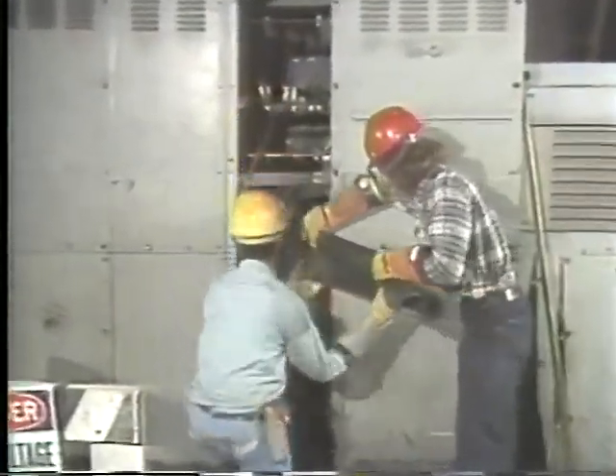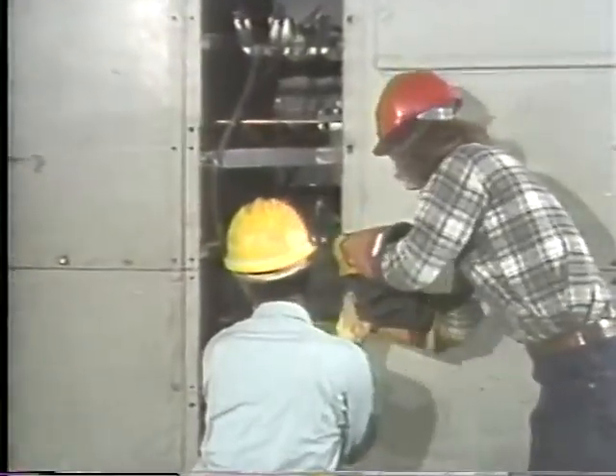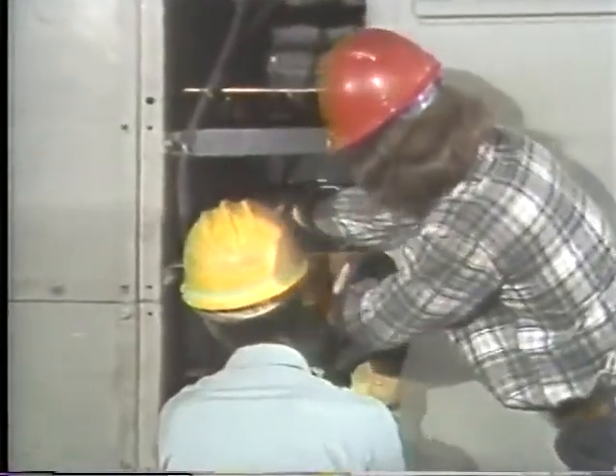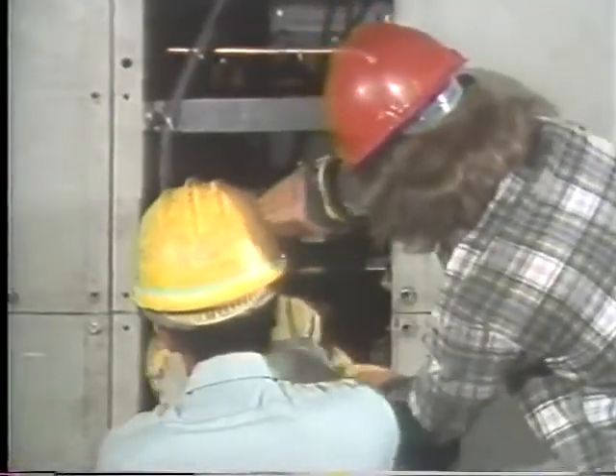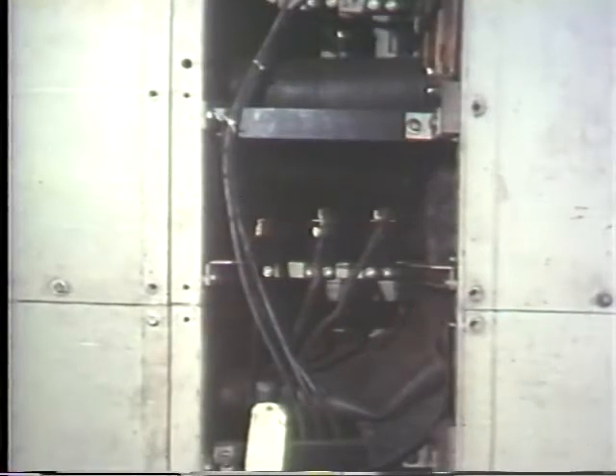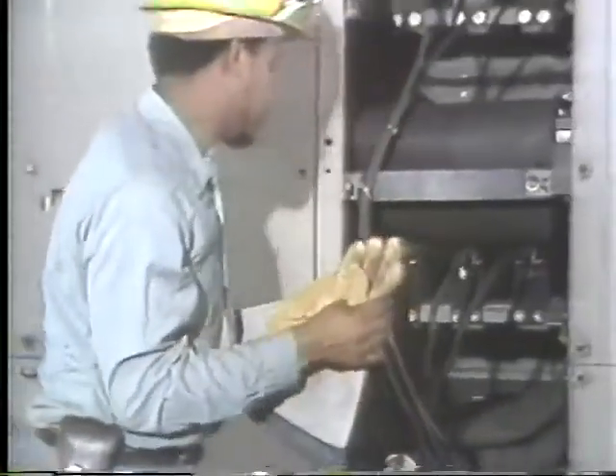The next part of the job, then, is to cover the exposed main bus with rubber blankets. The bus bars run under, up the side, and over the terminals in question. So all three sides of the bus have to be covered with the blankets. Now it's almost impossible for the electrician's hands to come in contact with the hot bus bars. Before removing his gloves, though, he makes a last check to be sure that all the nearby bus bars are completely insulated. Then it's safe to take off his gloves and go to work.